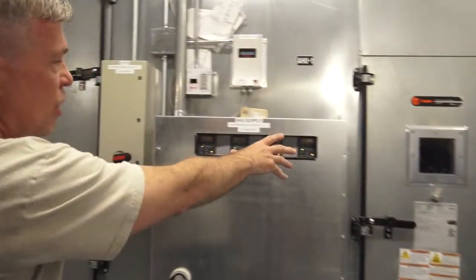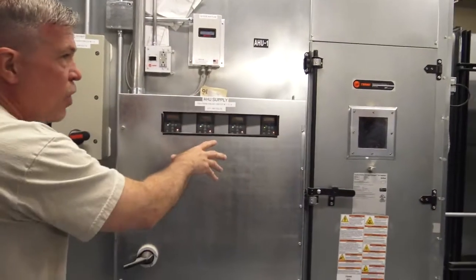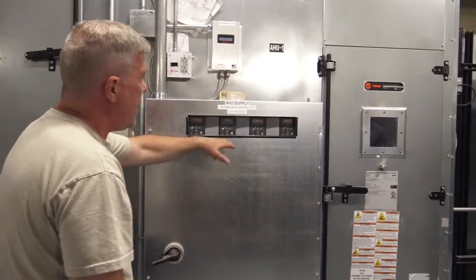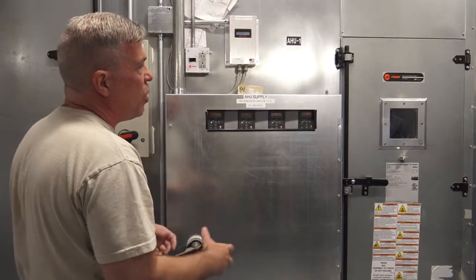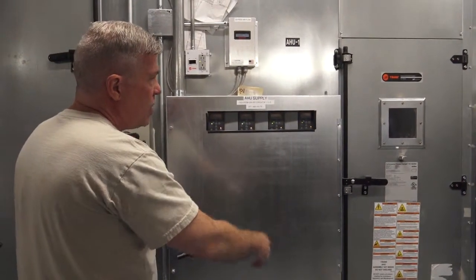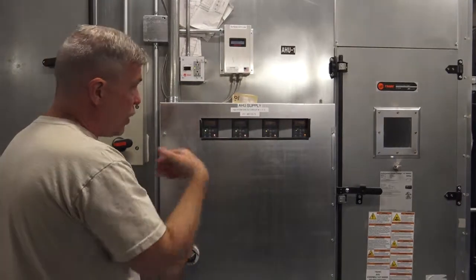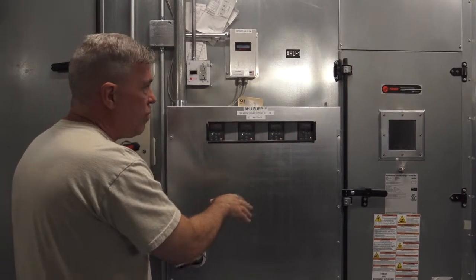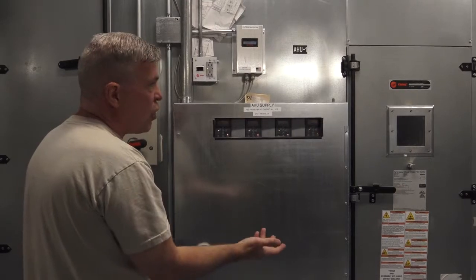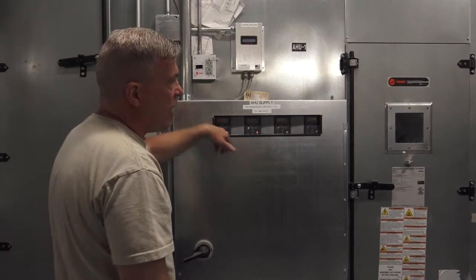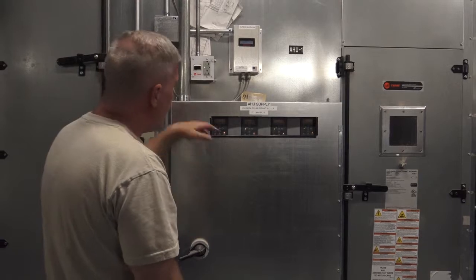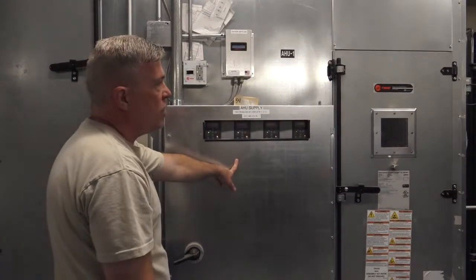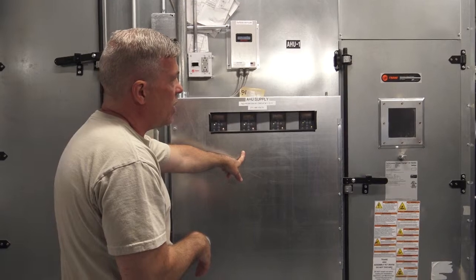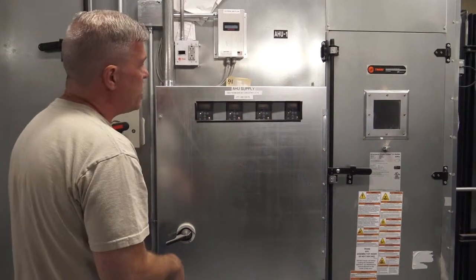So we'll walk through the air handler then. Air handler starts with the supply fan section. There are 4 supply fans, 4 drives. Each fan has an individual drive, but they're all controlled as one big fan. So on your graphic, there's only one start-stop for it. It's turning all of them on, with one speed control. But you do have individual status and failures for each fan. So if fan number 3 fails, you'll get a failure showing that fan is the one not functioning. The rest will continue running, making up the difference.